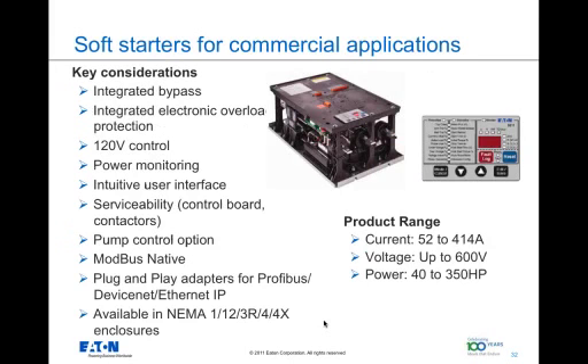Now, the commercial construction segment does ask for the high-end feature set. However, they need those at very economical cost points, and we have a product just for that. The S611 does deliver the functionality which the commercial construction and the high-end OEM market is looking for, and that includes the integrated bypass, integrated overload protection, the 120 volts control, doing away with any of the power supplies that are needed for any conversions, power monitoring, intuitive user interface, a user interface which can be used for real quick commissioning without needing a quick start guide, serviceability in the field.